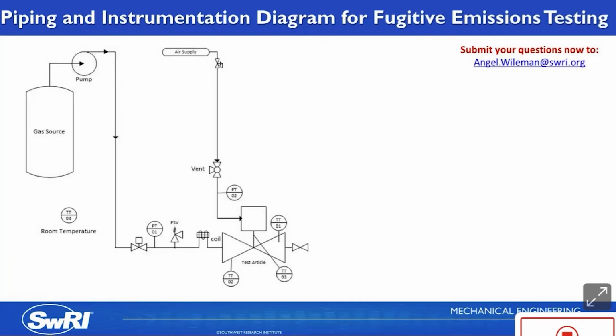So what does a test stand look like for fugitive emissions testing? Here is a typical setup. You have your thermocouples placed on the valve, like we just discussed. You have a pressure transducer upstream to measure the gas pressure being applied on the valve. A positive displacement pump can be used to pump up the source gas to your target pressure, and that can be with helium or methane. We have an isolation valve installed downstream of the valve, which will be closed so you can build up pressure in the valve. Now, you could also just have a blind flange on the end, but make sure whatever you're testing to doesn't require a through leakage measurement, or else you can install a valve and open it as needed with a mass flow meter to get your through leakage.